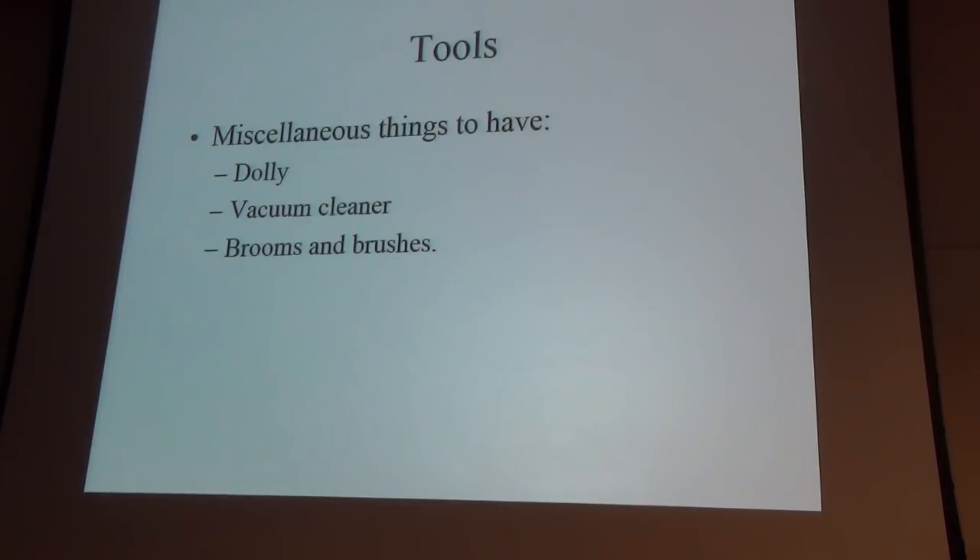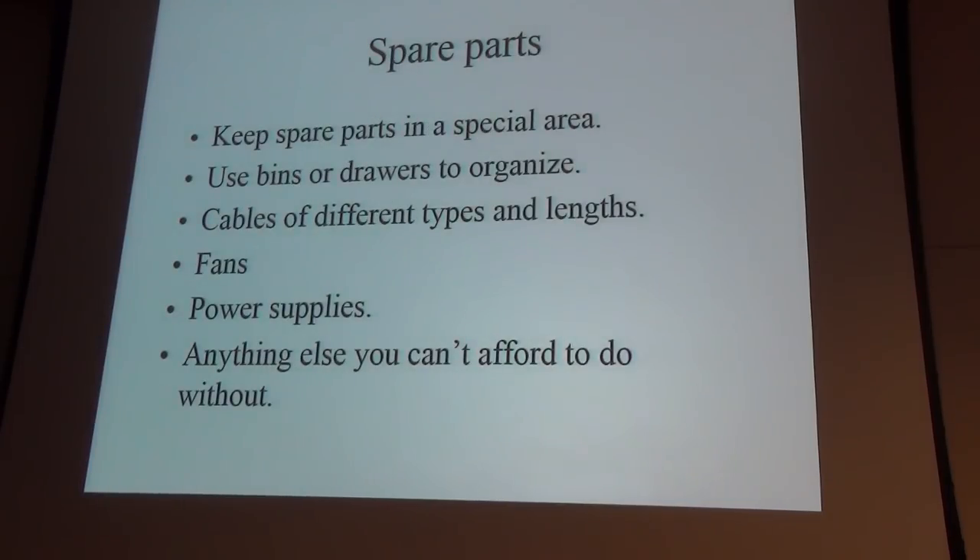Make sure the person cleaning the data center uses modern vacuum cleaners that don't put out a lot of EMF — just like the TV picture distorts when someone vacuums near it, the same happens in server rooms. Have spare parts organized — you never know what you need. I've had a whole installation held up because of one wrong connector. On the bill of materials, the SKU was off by one digit, and we even had someone claim they sent the right one but all of them were the wrong gender. Have your own supply and make sure you're not violating any building codes.